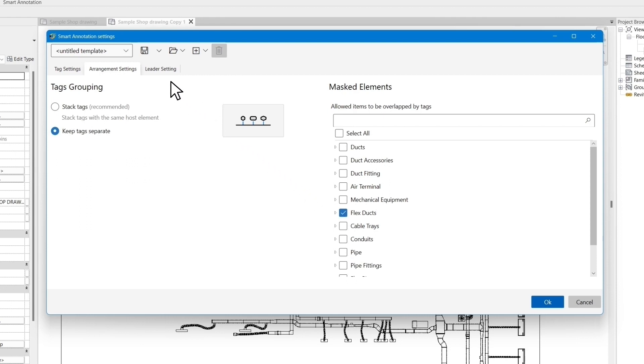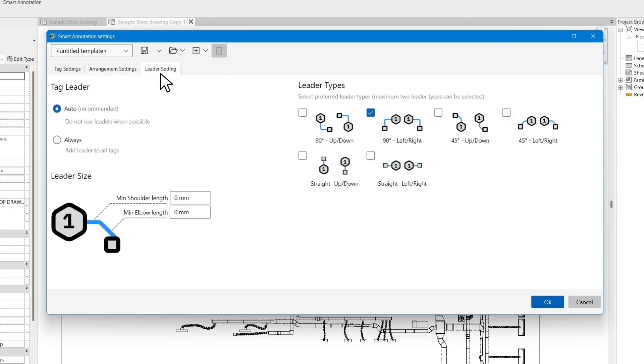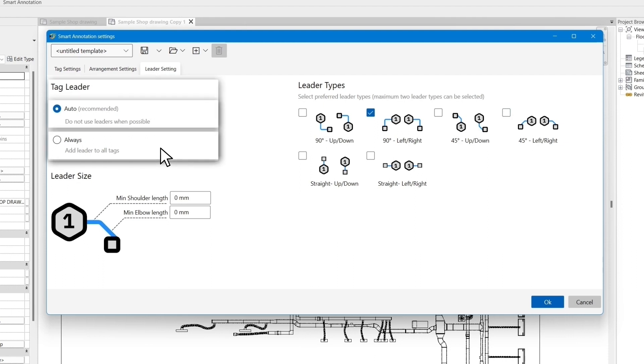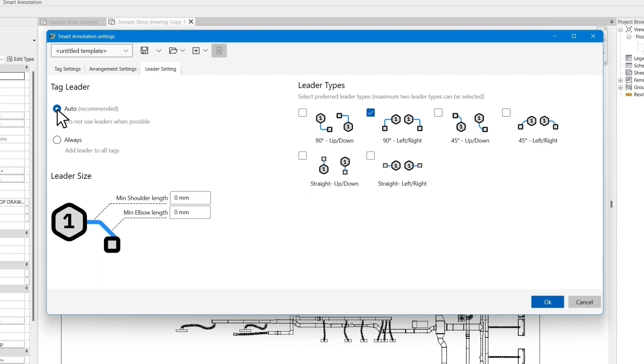The final tab is the leader settings. In the tag leader section, you specify if you would like to have leader lines for all of your tags or allow the app to minimize the leaders where it is not required. If you select the auto mode, the app will only put leader lines for the tags that are outside of objects and have to be placed further from the element. You can also pick the leader types you would prefer on the right side.